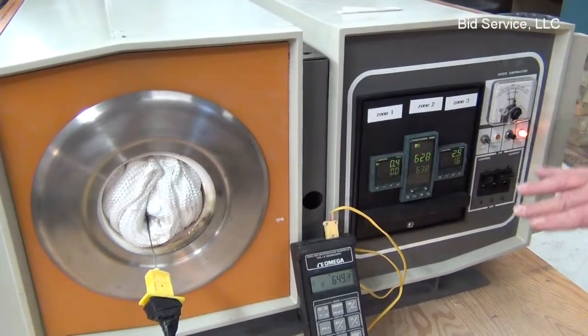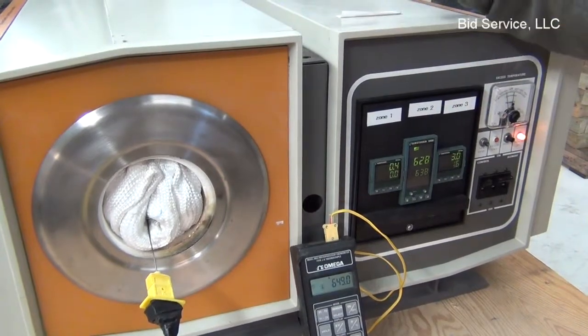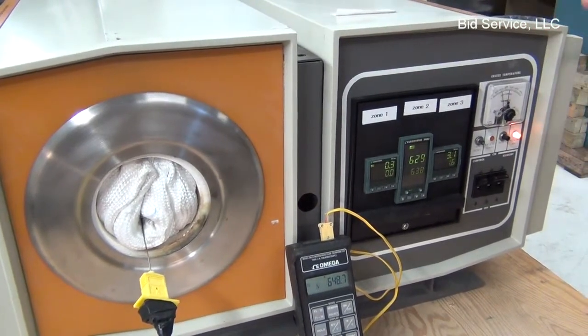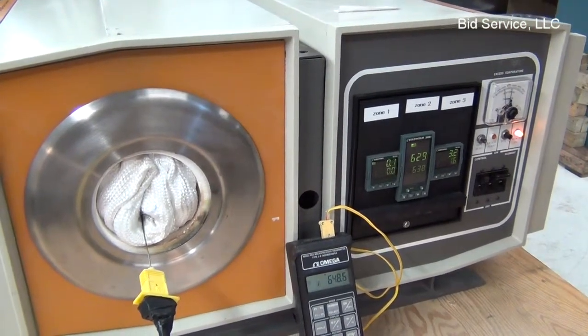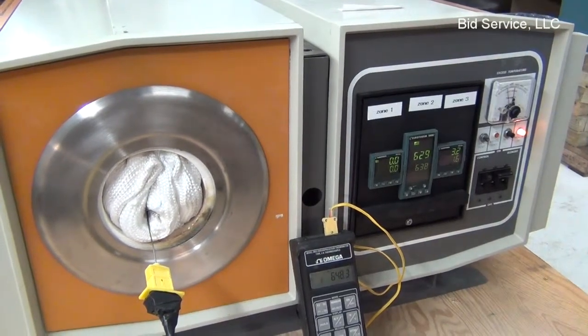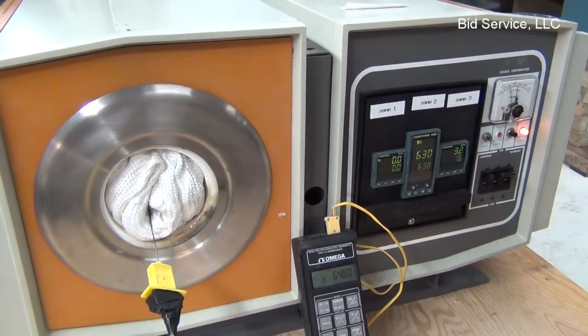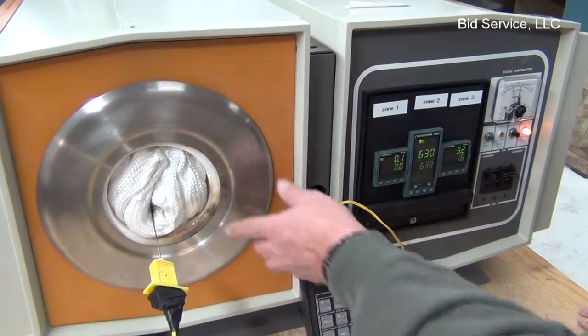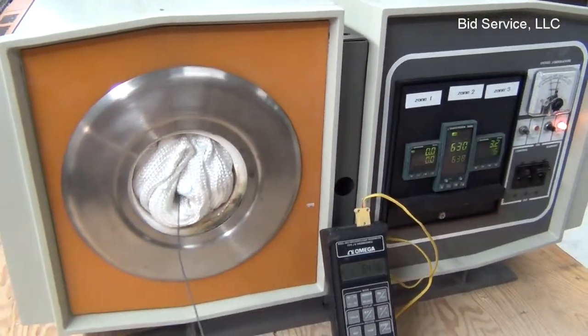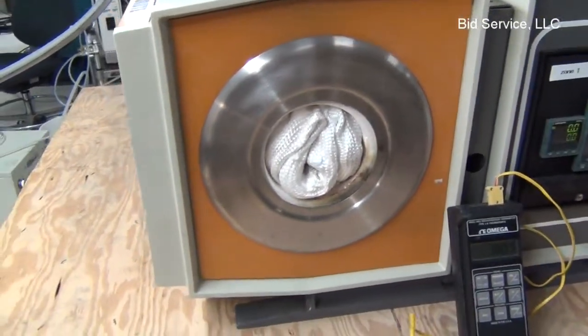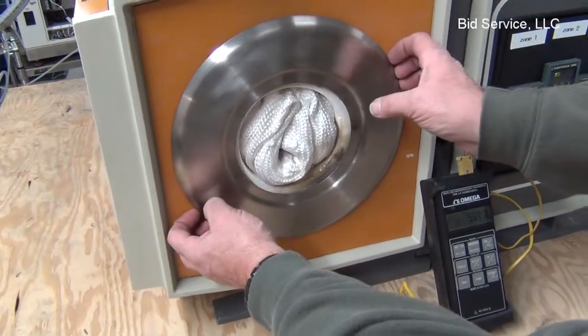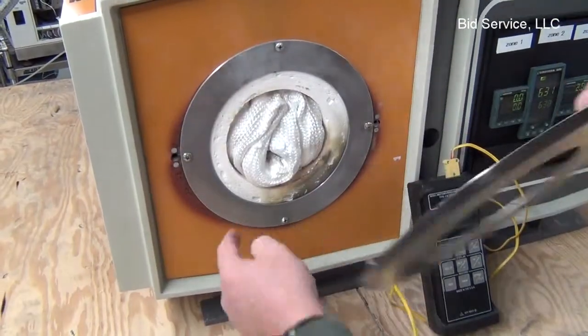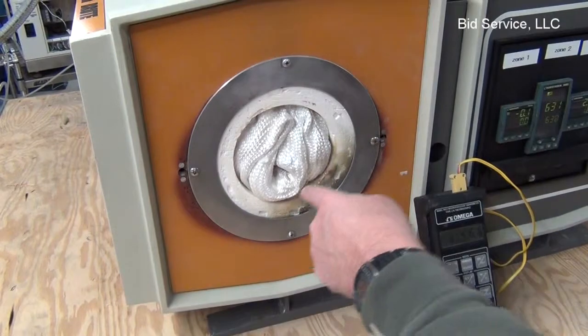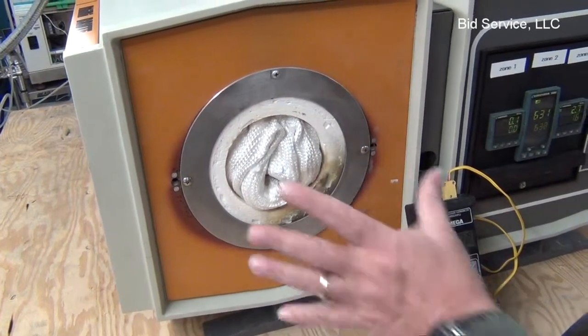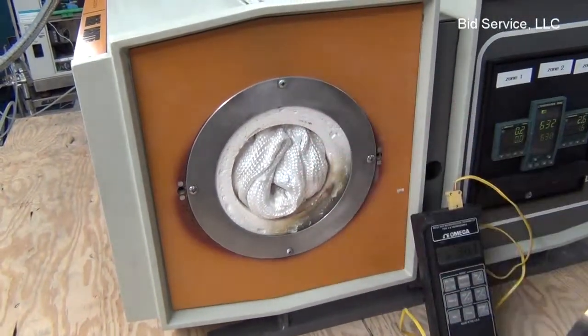The only other things I want to tell you about is that the power for this instrument requires 48 amps. So that's at the minimum, so you need a circuit that will be able to handle that kind of current. And lastly, besides these plates, let me pull this out. Okay, there's these inserts. They are consumables. They do not come with the unit, so they will be removed before it's shipped.